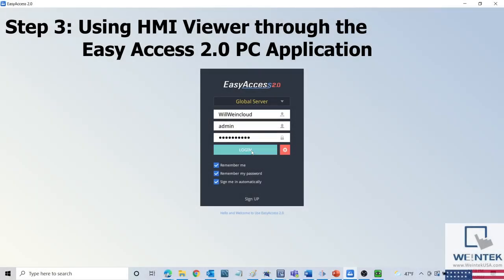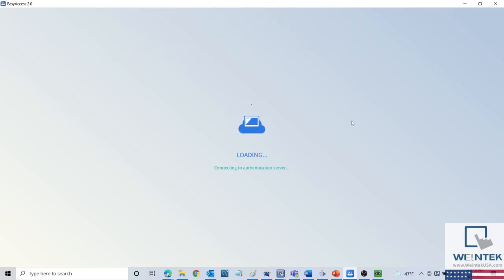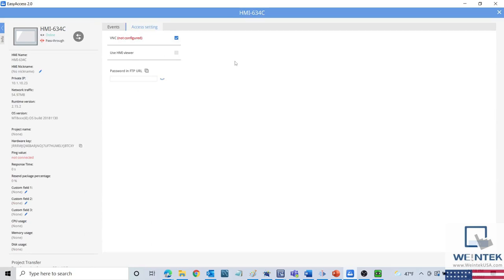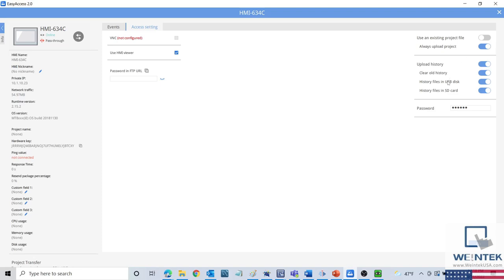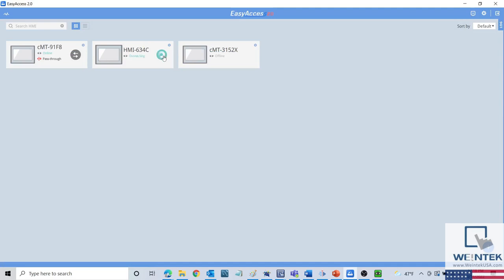Now that the HMI has been registered to your domain, log into the Easy Access 2.0 application with your WeinCloud credentials. If your HMI is connected to the internet, you should be able to establish a connection by clicking the inward-facing arrows. However, before doing so, click on the HMI's icon and navigate to the Access Settings tab. Here we can select one of the available remote monitoring options. Click on Use HMI Viewer, select Upload Project, and enter in the HMI's password, then press OK. Now click on the inward-facing arrows to establish a connection between your PC and the HMI. You should see a blue icon appear under the inward-facing arrows — this button will open HMI Viewer.